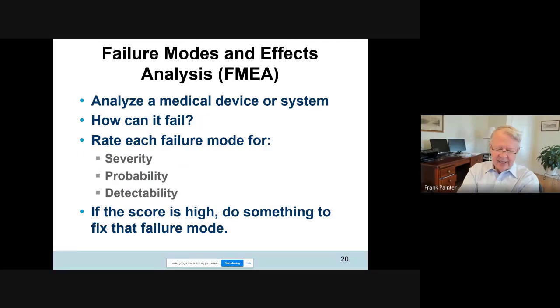So now there is actually a technique that's called failure modes and effects analysis, and we don't have the time to talk about this in detail, but it's based on the principles that I just talked about. Now, this failure modes and effects analysis is required by many different organizations. So, for instance, when the Food and Drug Administration in the United States allows a medical device to be used on patients in the hospital or anywhere in the United States, they tell the manufacturer, okay, great, you've created this new device, or you're manufacturing a better version of an old device. You need to do a failure modes and effects analysis on all the ways that this device can fail, so that you can either say that the risk is low, or you can change your design to reduce the risk, because we want low-risk devices to come into the marketplace.